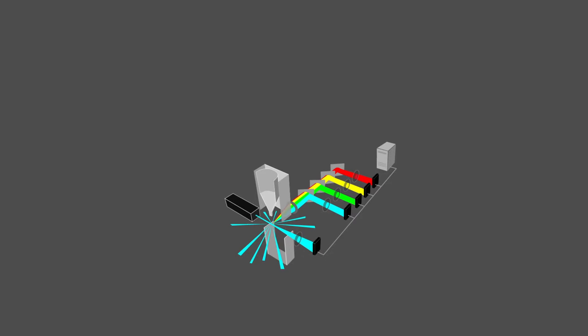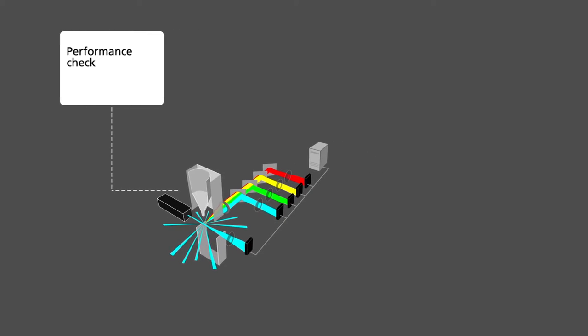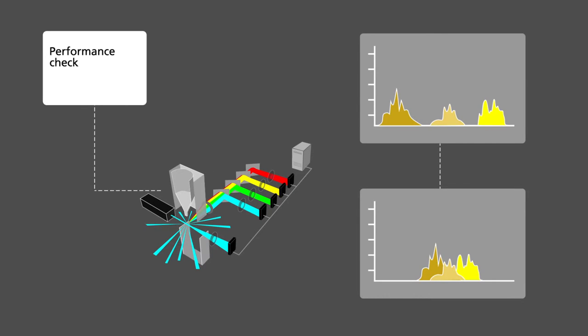The performance check is often made every time we use the machine to be sure that the baseline has not drifted. For instance, we make adjustments in PMT voltage for each parameter input.